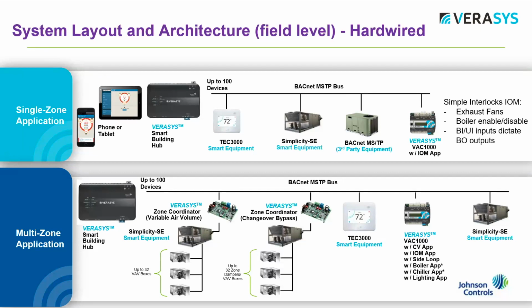If we go above 2 and 2, we would then use one of our VAC application controllers that you see on the far right of that screen. And it can handle, I want to say, like 5 cool and 4 heat stages. It also will give us the opportunity to do, for example, combinations of DX cooling and hot water heating, or chill water cooling and hot water heat. We have all those applications that are then easily selectable and configurable with the product itself.